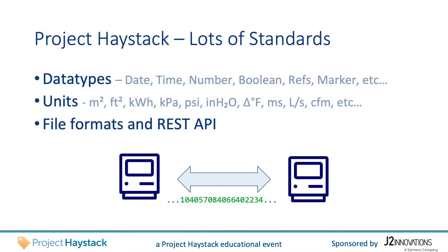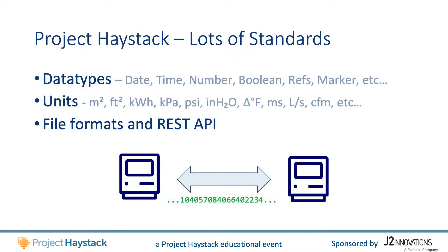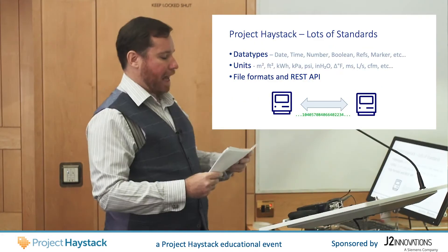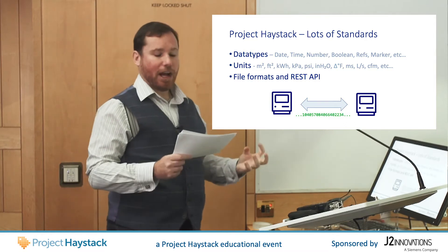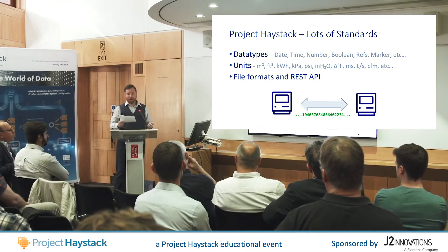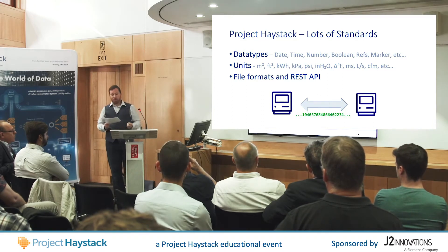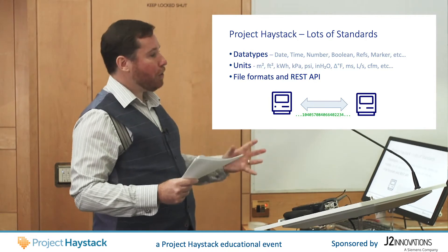Project Haystack is more than just a tagging standard. It's about interoperability between different computer systems. It defines the types of data that can be tagged — dates, times, numbers, booleans, references and so on. And if you have a number, Project Haystack also defines the units, so we know if we're talking about square feet, square meters, pascals, degrees Celsius, whatever. When kitting out a building, we're going to have lots of different devices, computers and equipment from different vendors. So Project Haystack defines file formats, so your cheap Chinese temperature sensor can seamlessly talk to your gateway. In today's age of Internet of Things, everything is networked, so Project Haystack also defines an Internet REST API. It's all about communication and interoperability so you can avoid vendor lock-in.